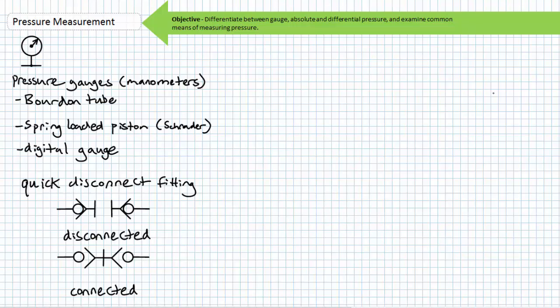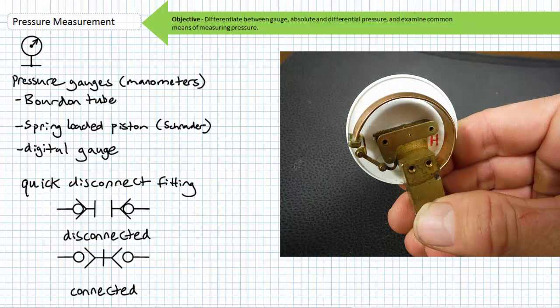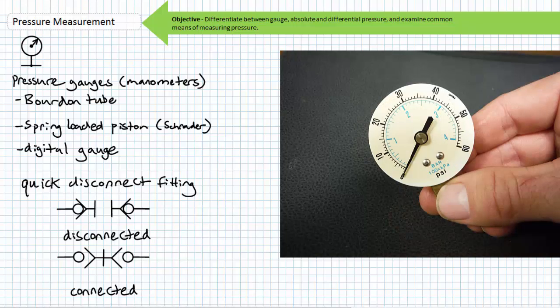Two common types of analog pressure measurement devices are Bourdon tube and spring-loaded piston gauges, sometimes called Schrader gauges. Both methods necessitate a passageway to the fluid under pressure. A Bourdon tube is a curved metal tube linked with a pointer. When pressurized fluid enters the curved metal tube, the tube is distended and the mechanically linked pointer moves along the calibrated scale like the hand on a clock. Sometimes the dial and Bourdon tube pressure gauges are oil dampened to limit erratic movement of the needle or cushion it against surges. The schematic symbol for a pressure gauge looks astoundingly similar to a Bourdon tube pressure gauge.